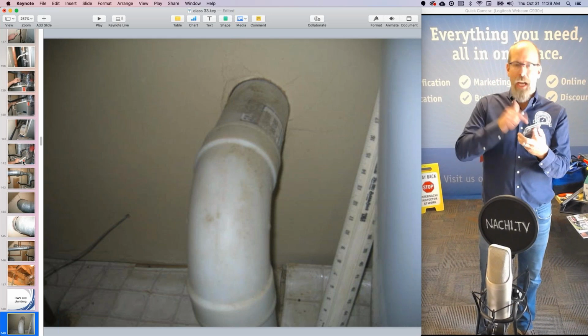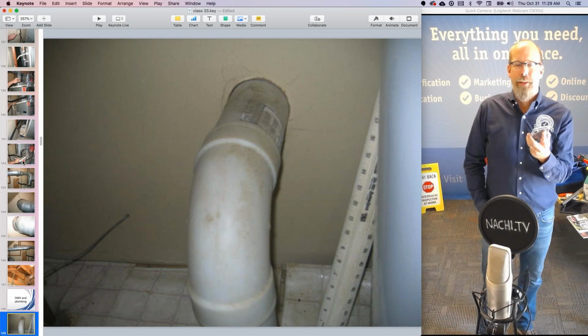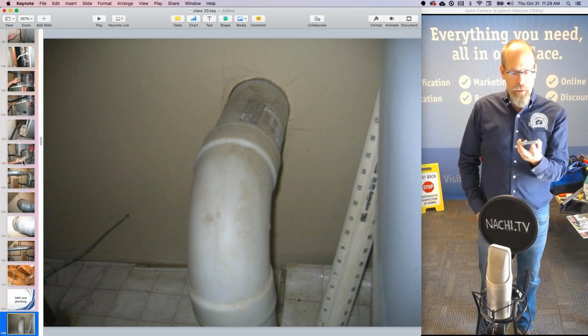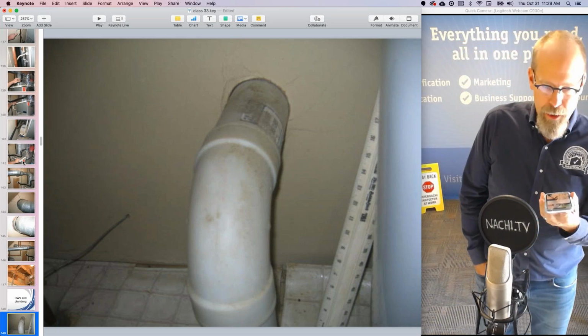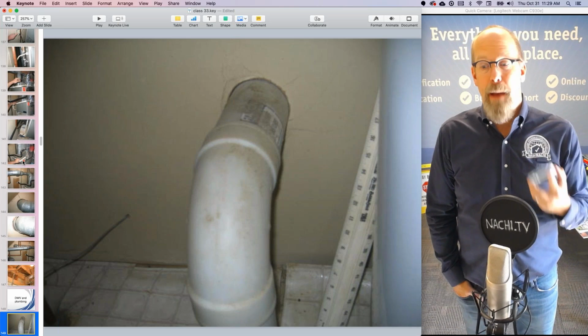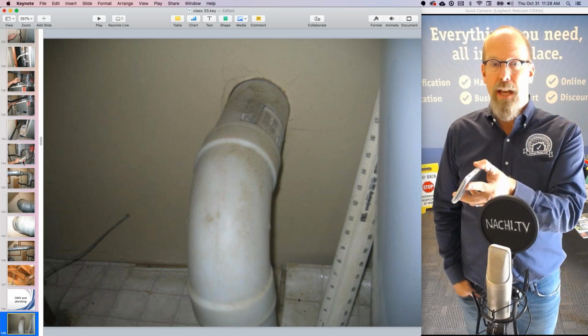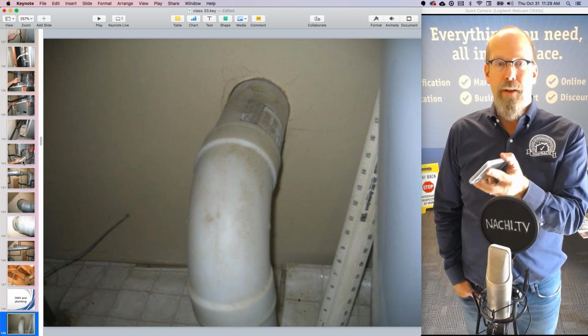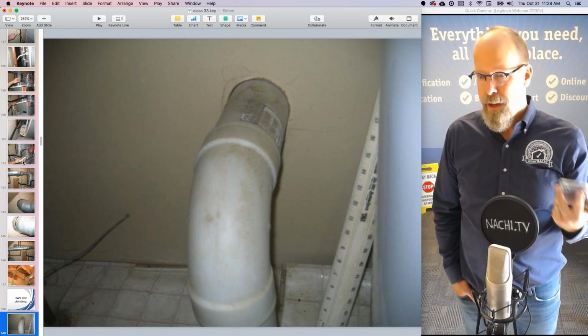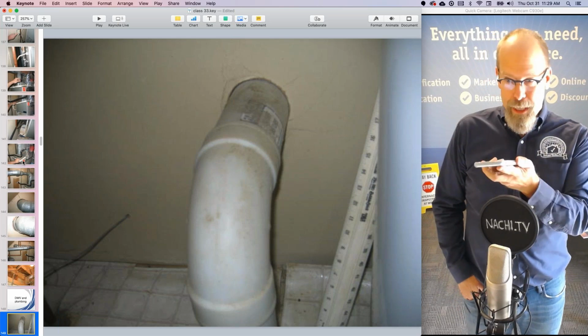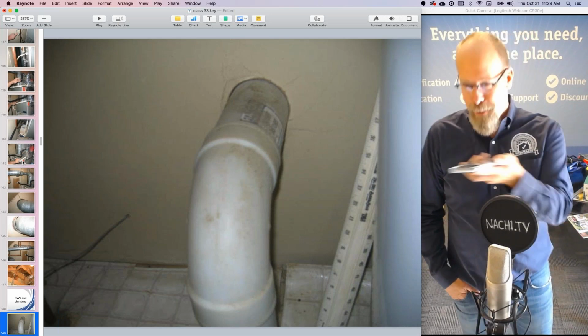I have a checklist on how to inspect all of the features of a well-performing radon mitigation system. I bet this system was installed a long time ago. It doesn't have a couple of features that I'm looking for, like a manometer and a good sticker that's easily readable.